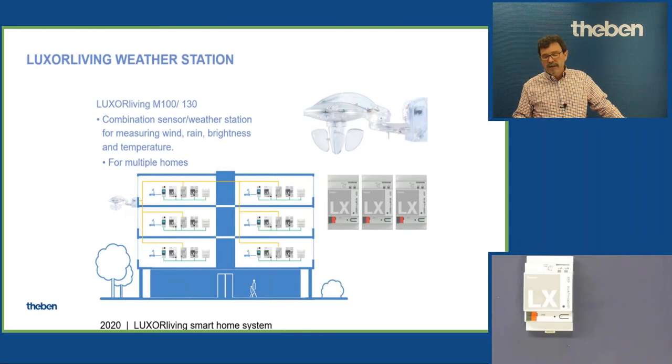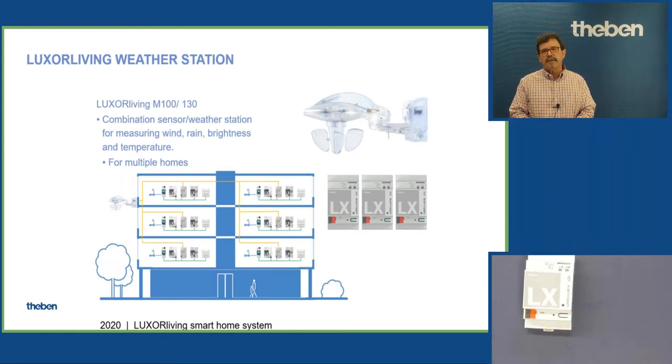This is just a single communication you discover here in this drawing. This is a yellow cable, and this yellow cable is just looped from device to the next device, but it is not linked to the communication in the different single family flats. So that means there is no chance at all to scan, for instance, the applications or the statuses of the neighbor, the flat in the neighborhood, because this is not standardized communication. It's not KNX based and not related to the bus communication which we have here. Totally separated. And I think it's a good argumentation.